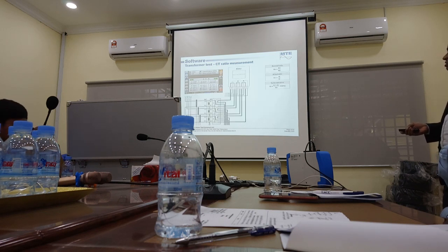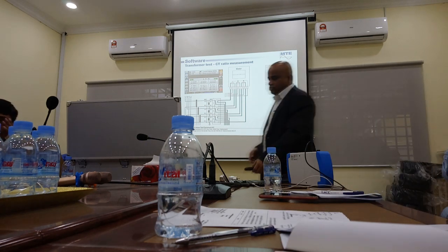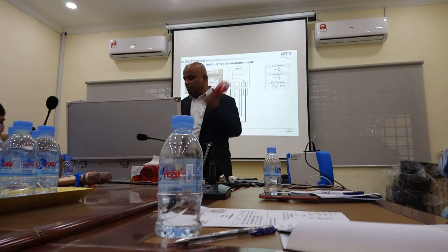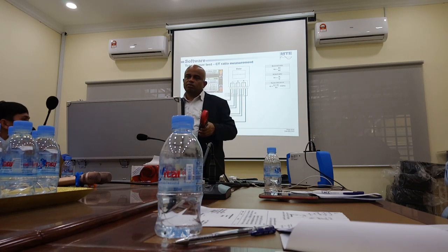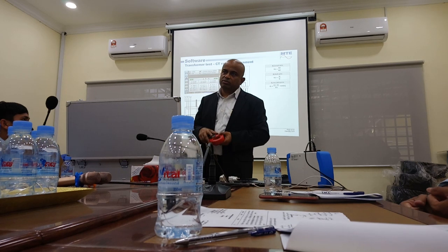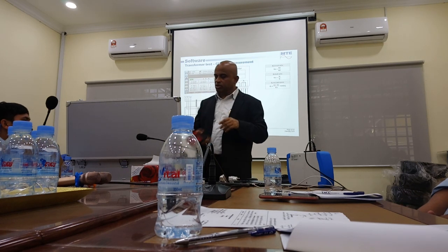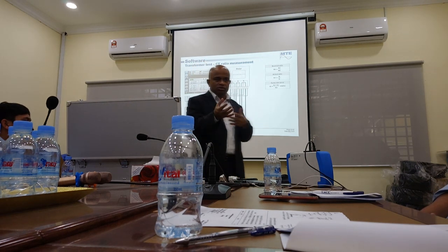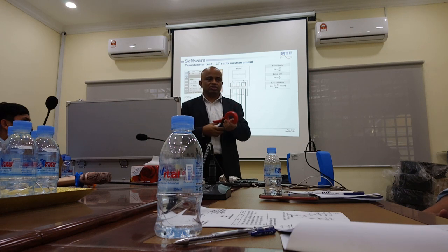Same with CT ratio also. You take two sets of clamps. Maybe on the LV side, if you have a high current CT, you use this and one on the primary, or maybe the other way around. And you can straight away measure the accuracy. But these CTs are not good for medium voltage, only for low voltage. For medium voltage, isolation is very important, so you may need to use a hot stick.